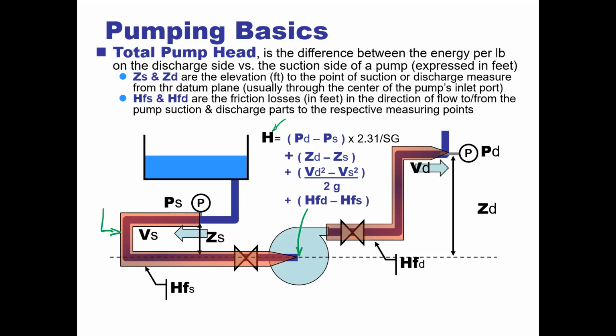You have to overcome friction loss by increasing your pressure. Why wouldn't that be something a designer would figure out? Why would it be necessary for you? Because gravity is in effect all the time, and not just gravity, but the length of our pipes. We may run into situations the designer never thought we'd be in.